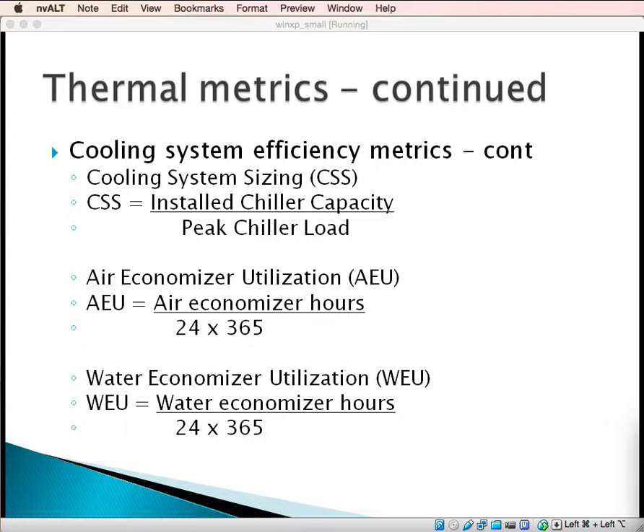Cooling system sizing, or CSS, can be used to determine the scalability and potential of the current cooling system. AEU is useful for data centers in colder climates, where an air economizer can be used to provide free cooling during certain parts of the year when it's cold, instead of using a chiller plant.